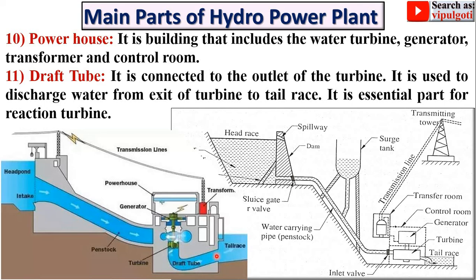The draft tube runs from the turbine outlet to the tailrace. It is used to discharge water from the exit of the turbine to the tailrace. It is an essential part for the reaction turbine. So the draft tube is particularly used for the reaction turbine. If the turbine is a Pelton wheel — that means an impulse turbine — then the draft tube is not required.